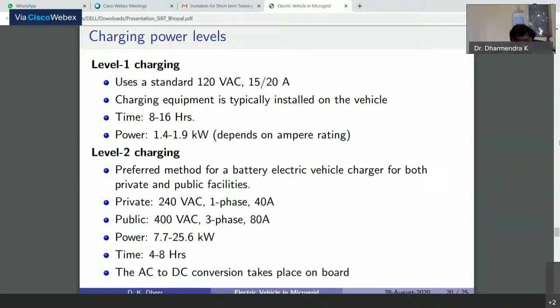Level 2 charging is the preferred method for battery electric vehicle charging for both private and public facilities. For private use, it's 240 volt AC, single phase, with current rating of 40 ampere. For public use, it's 400 volt AC, 3 phase, with current rating of 80 ampere. The power rating of level 2 charging is between 7.7 kilowatt to 25.6 kilowatt, and it takes 4 to 8 hours to fully charge the battery. AC to DC conversion takes place here as well, since from AC we have to supply DC.